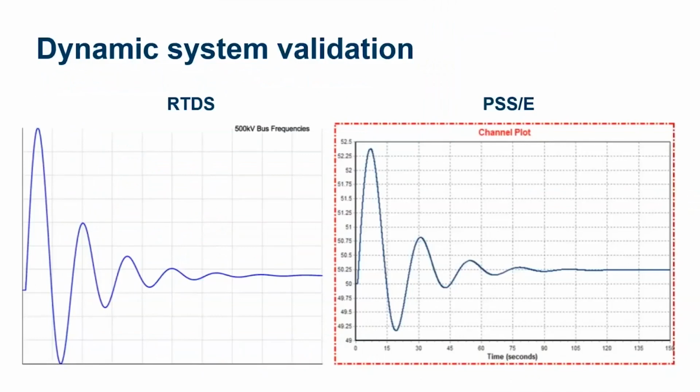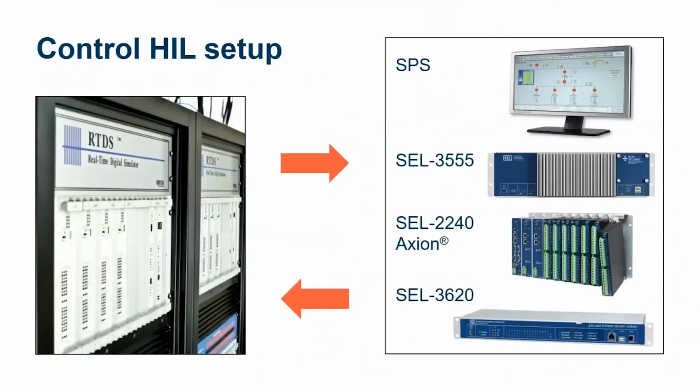Both validation methods help build a test bed that is apt for simulating the severity of the system. At SEL, we perform controller hardware-in-the-loop testing during factory acceptance testing. This not only allows us to deliver a control system of the highest quality, but also acts as an insurance plan to avoid any potential modifications in terms of requirements, cost, and schedule impacts.